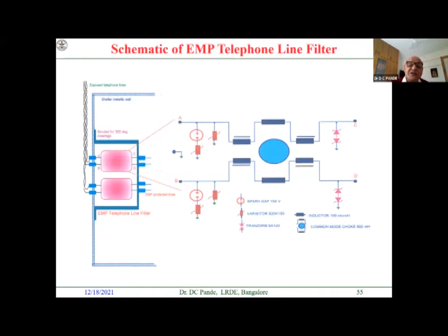Power lines also have this aspect: after the circuit breaker, we put filters because the circuit breaker won't respond fast enough. Circuit breaker responds in milliseconds, but the pulse I mentioned comes in nanoseconds, so we need protection by very fast devices.